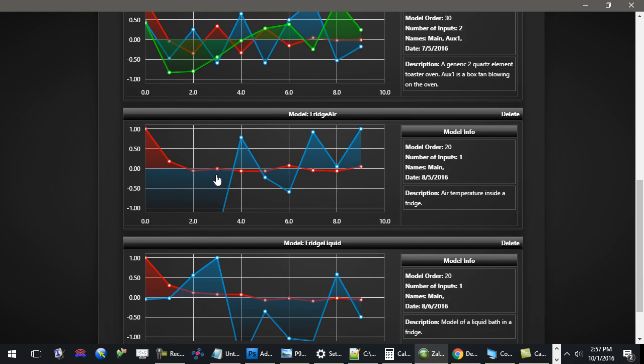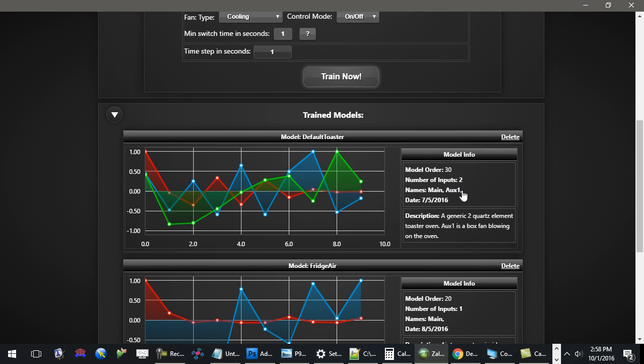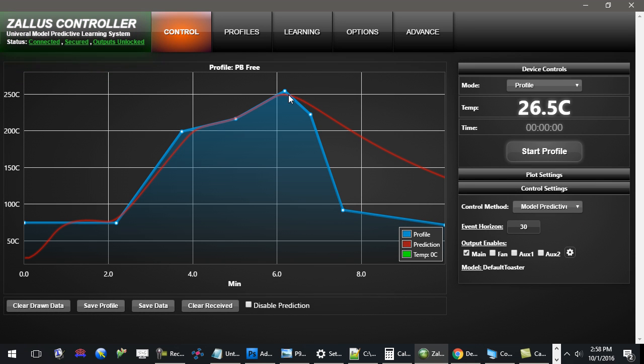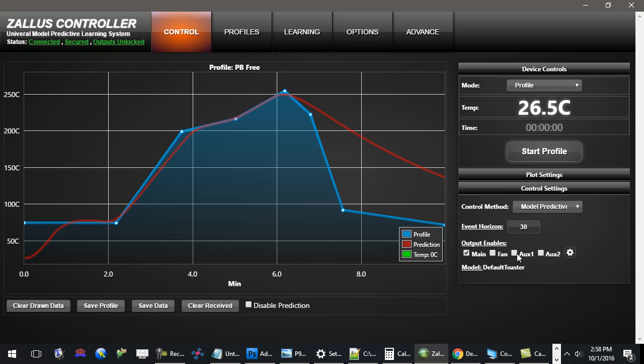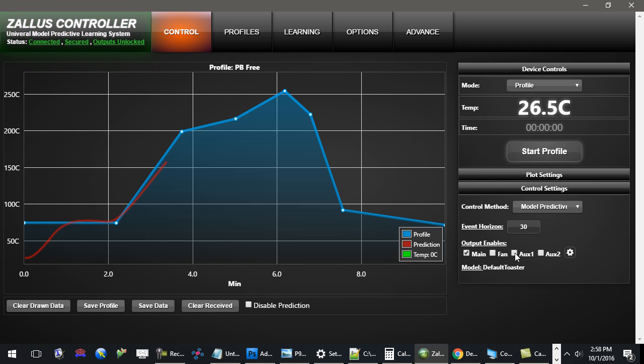For example, when I first trained this system with the oven, I configured one of the inputs to be a cooling input. With my profile, I try to tell it to cool down too quickly. However, when I trained the system, there was actually a box fan pointed at it, and so it learned the characteristics of that box fan and how it would affect the system. You can see when I enable that output, it will control the system better and achieve better cooling. You can learn what various outputs do as well as their effects on the system and how they can improve control.